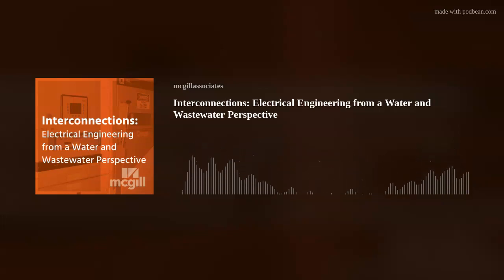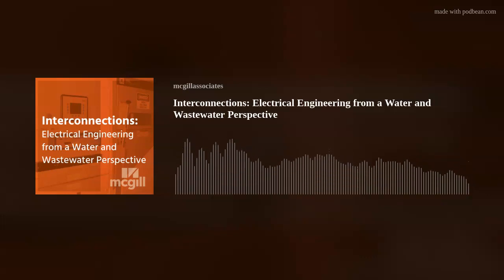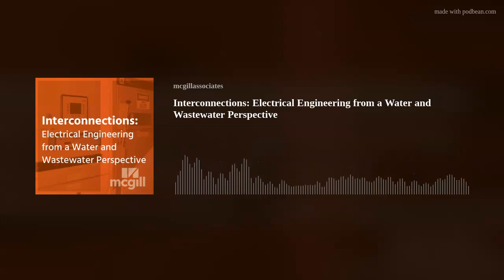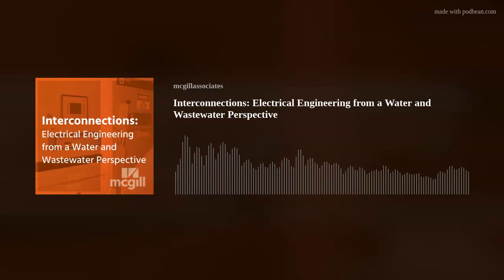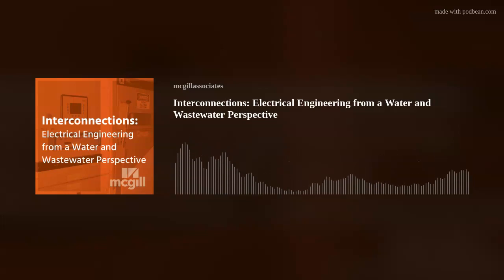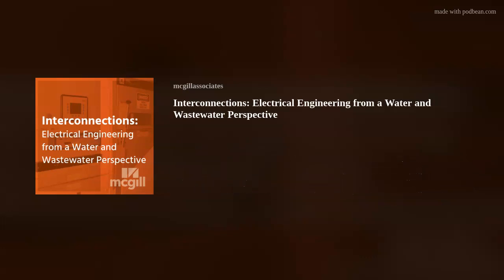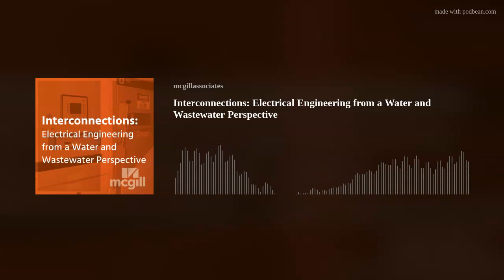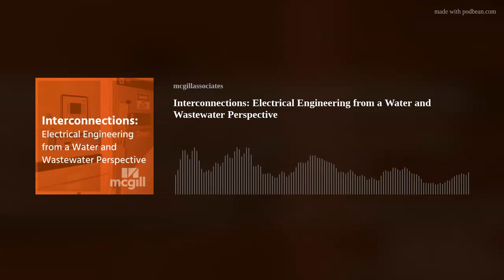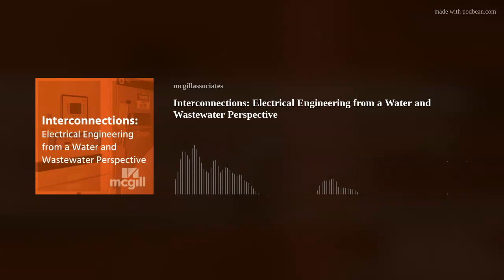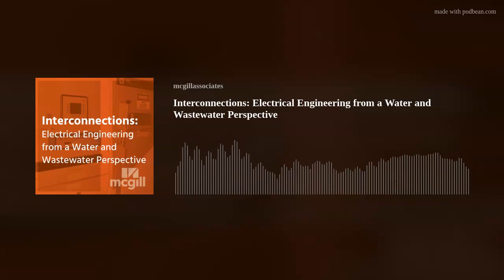So, what kinds of issues do you see when updating older SCADA equipment to new equipment? Are there difficulties connecting older technologies to modern technologies? Absolutely. Over the lifespan of a plant, we've been in plants built in the late 40s, early 50s, and those plants have seen tremendous add-ons and upgrades throughout the years. One system in particular that we go in and see started in the early 80s, some of the SCADA systems and the PLCs associated with those. PLC stands for programmable logic controller. Just like any other computer system, as one is designed, they're always working on the next design, with more functionality and more computer power replacing the older ones.